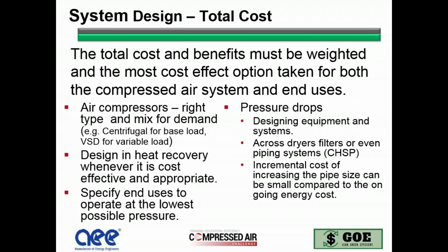One of the examples that I have is the system that I had at Chicago Stamping when I was the Powerhouse Chief. We were pushing 25,000 CFM through a 14,000 CFM dryer, and it was causing about a 12-pound pressure drop across it, and obviously not drying very well. With that amount of pressure drop and the fact that they were large centrifugal compressors, I was able to write a cost savings project to put in 2 new dryers and a building addition for what that costs.